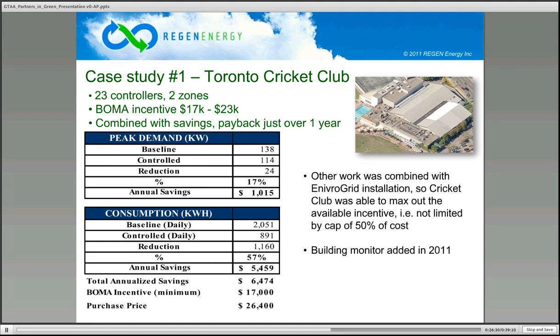Combined with the savings, including the incentive, the payback was just over 1 year. For peak demand baseline, uncontrolled, they were using 138 kilowatts as their peak in a month. With the controllers on, it was 114, for a saving of 24 kilowatts - a 17% reduction. Their annual savings there were just over $1,000.